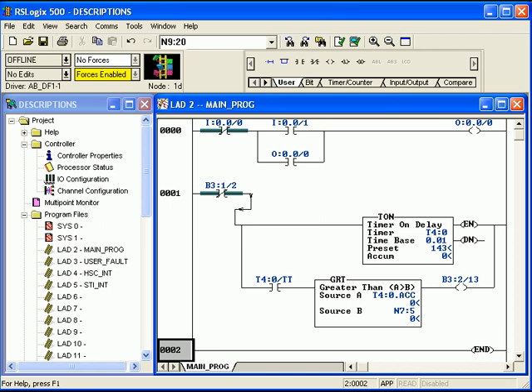So if you do go out and connect to a PLC on a machine to troubleshoot it and you do not have an offline project for that PLC's program, you will have to create a new offline project and then upload the logic into the offline project to view it. Even when you go online you're still looking at the offline project but you have basically animated the state of the memory locations displayed in the ladder logic on the screen. So if this is the case and you do not have any symbols or descriptions, you will have to reverse engineer the descriptions and symbols.